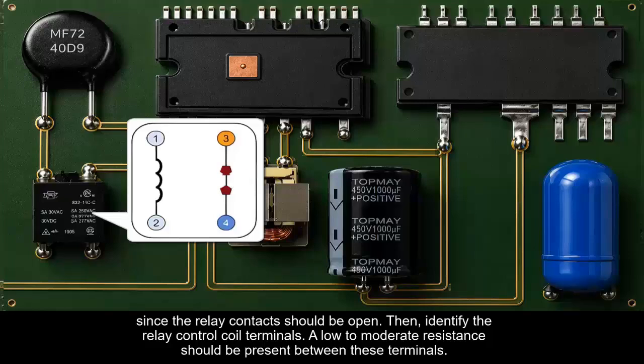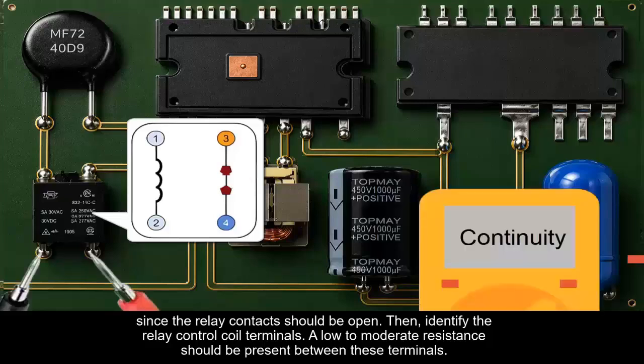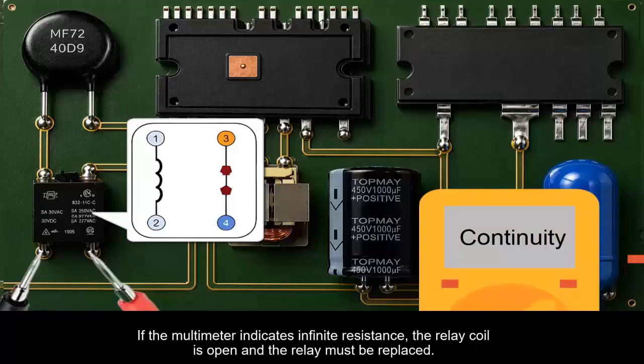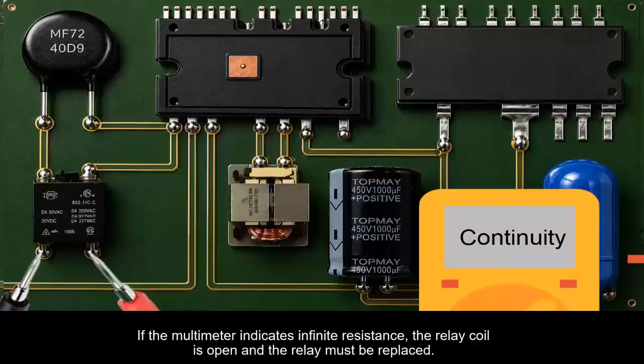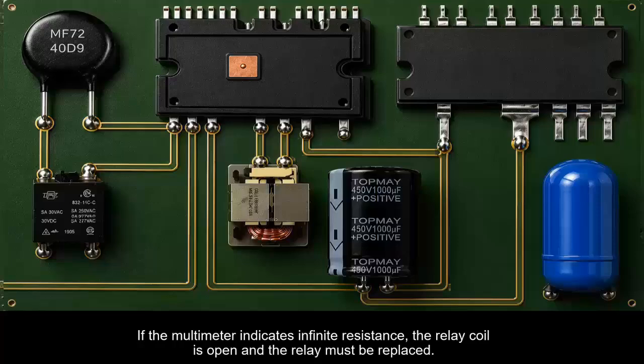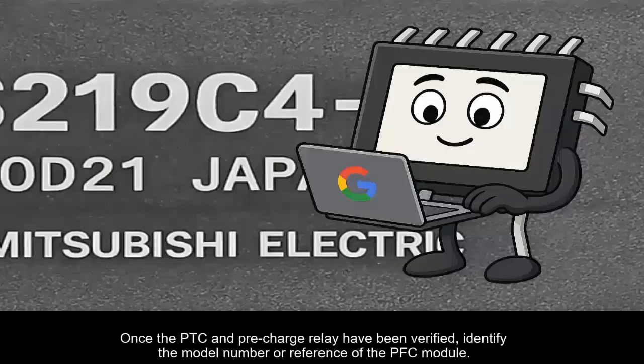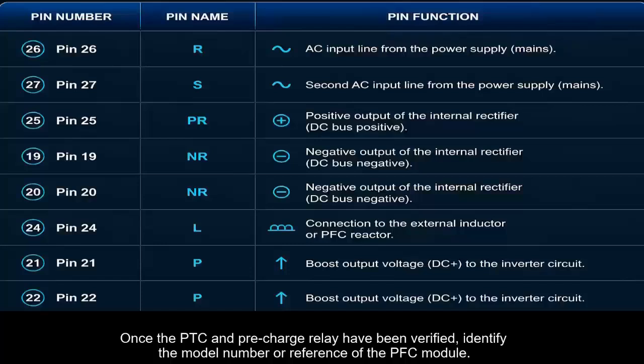A low to moderate resistance should be present between these terminals. If the multimeter indicates infinite resistance, the relay coil is open and the relay must be replaced. Once the PTC and pre-charge relay have been verified, identify the model number or reference of the PFC module. With this information, consult the manufacturer's datasheet to determine the function of each terminal or pin of the module.